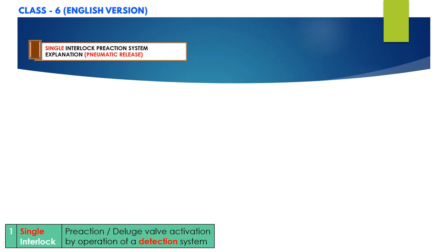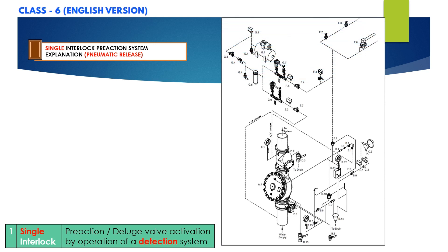Now let's discuss the pneumatic release type single interlock pre-action system. The concept is the same as the electric release type. In electric release systems, there is a dedicated releasing control panel with a compatible detection system — once the detector activates, it signals the panel, energizing the normally closed solenoid valve to open, releasing water from the priming chamber to drain, and allowing water to flow through the deluge valve to the complete system piping. Upon activation of sprinklers, water flows out of the piping network. However, in pneumatic release type systems, there is no releasing control panel or smoke or heat detectors.